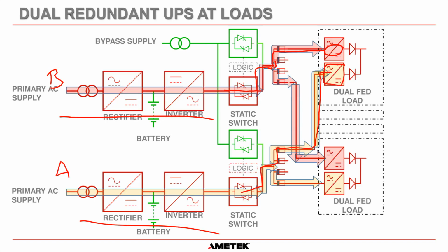Then these power supplies convert the AC into DC. There's a blocking diode on the output of each system so they don't backfeed each other. And then they are paralleled at the output of this point here. So if either of the UPSs fail, A or B, you still have one power supply that is continuing to feed whatever the circuits are in that dual fed load. This is actually a good system. It gives you really good redundancy still. It means you don't have the parallel logic. Now, we always have logic between the inverter and the bypass static switch, but these two UPSs don't have to speak to each other in this configuration.